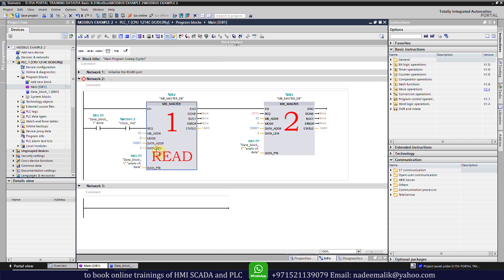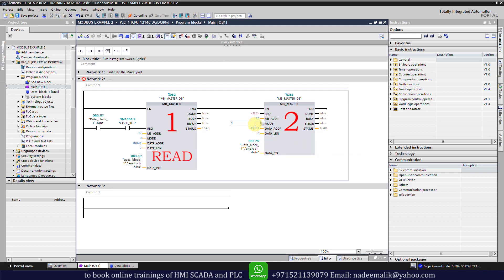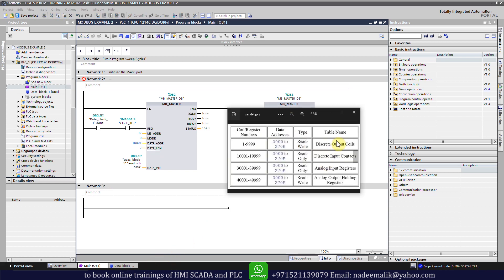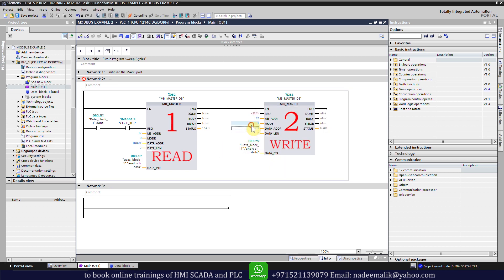Next we will leave everything else as it is. In the second MB Master function we will change the mode to 1, as we want this function to write the status of the outputs of this IO module — meaning it can now send data over Modbus to turn on or off the LEDs. We also need to change the data address for writing output registers; since the discrete output coils start from 1, we will enter 1 in the data address.